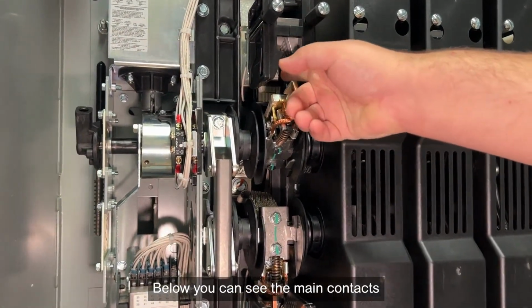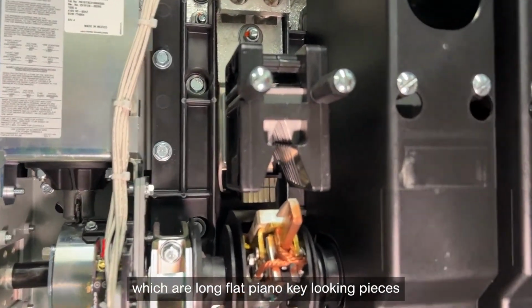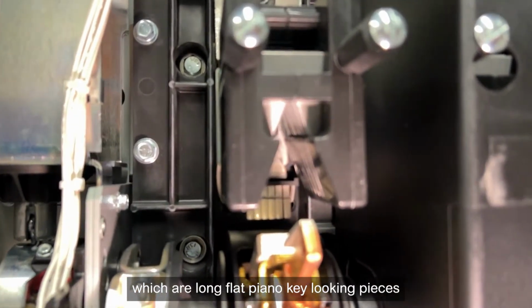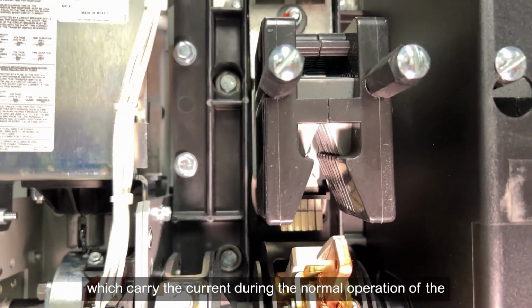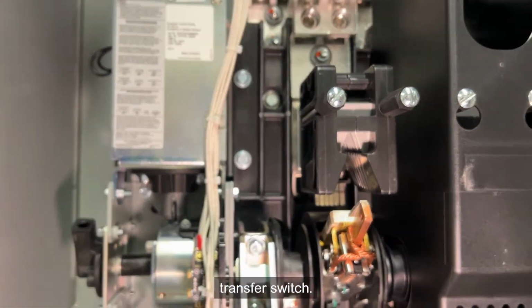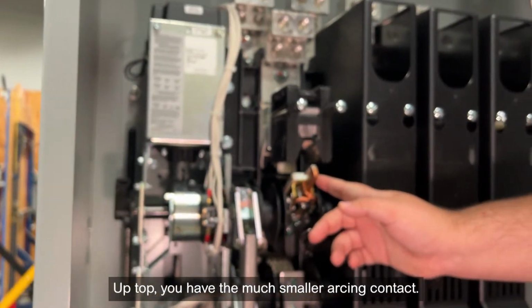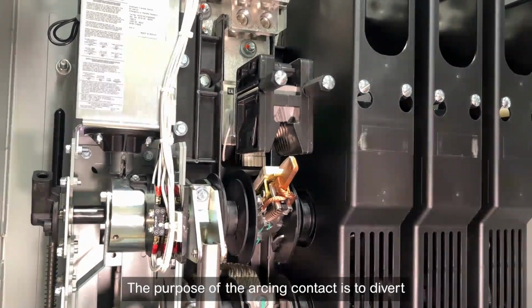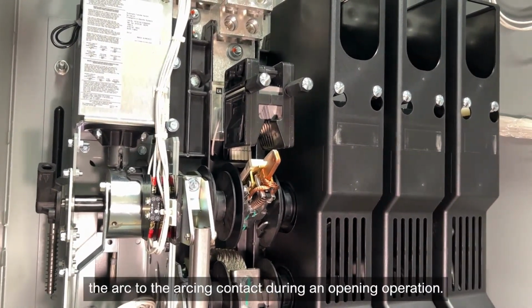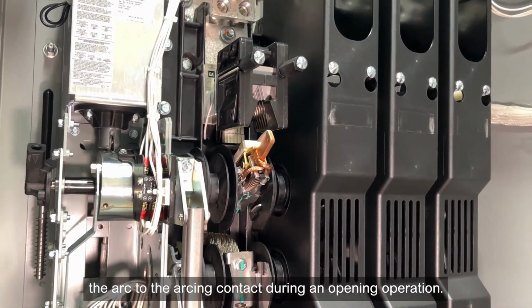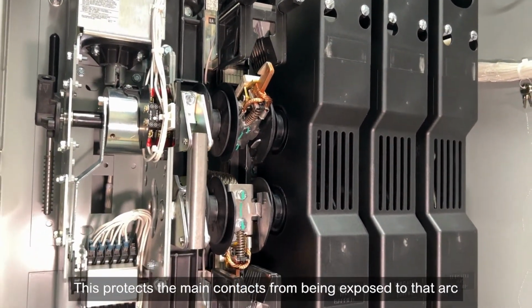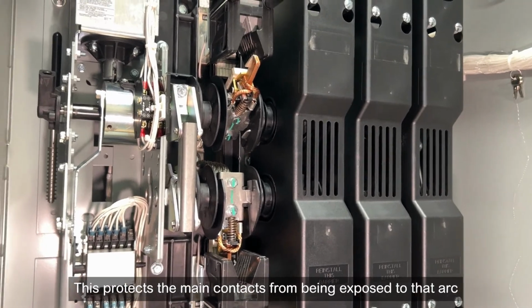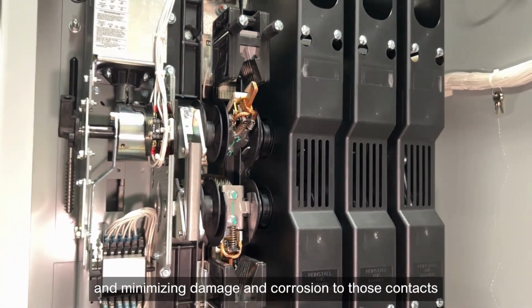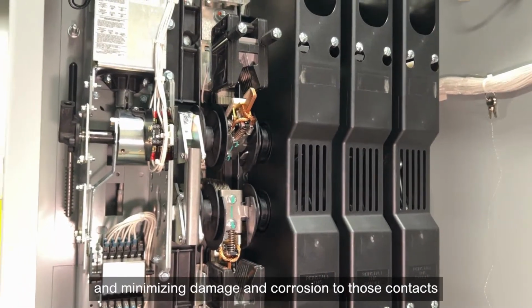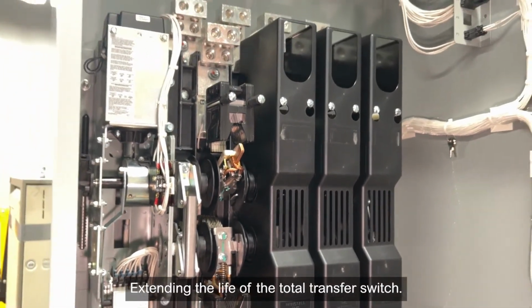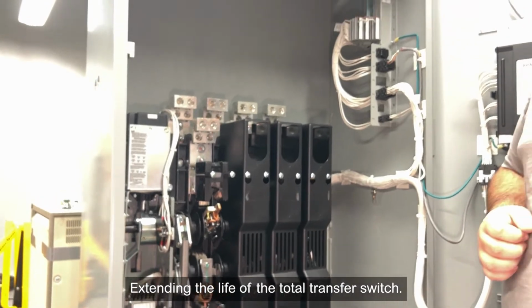Below, you can see the main contacts, which are long, flat, piano key looking pieces, which carry the current during the normal operation of the transfer switch. Up top, you have the much smaller arcing contact. The purpose of the arcing contact is to divert the arc to the arcing contact during an opening operation. This protects the main contacts from being exposed to that arc and minimizing damage and corrosion to those contacts during the operation of the equipment, extending the life of the total transfer switch.